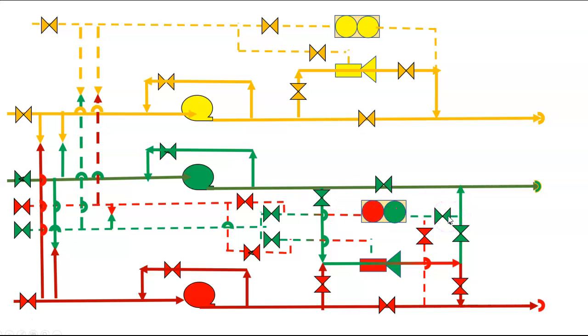This valve is open. Coming in through the green. This valve is open. Oops. This valve is open, and I'm discharging up and through here. So at this point right here, you have red cargo contaminating this line. If this valve is open, you're going to contaminate. But with these valves closed, I can keep my system pure. Green to green, red to red. So that's the proof that's in the pudding.